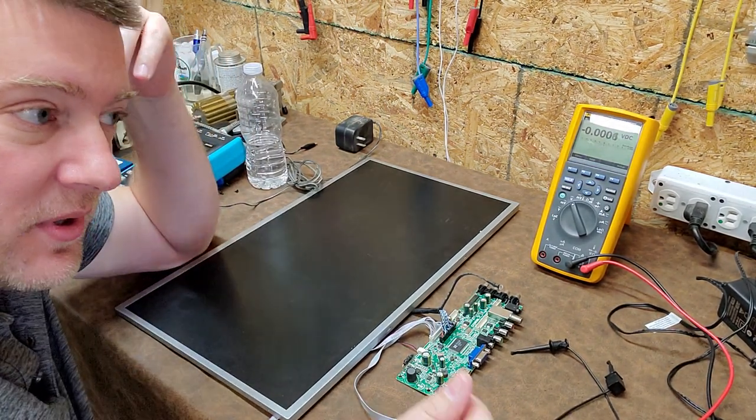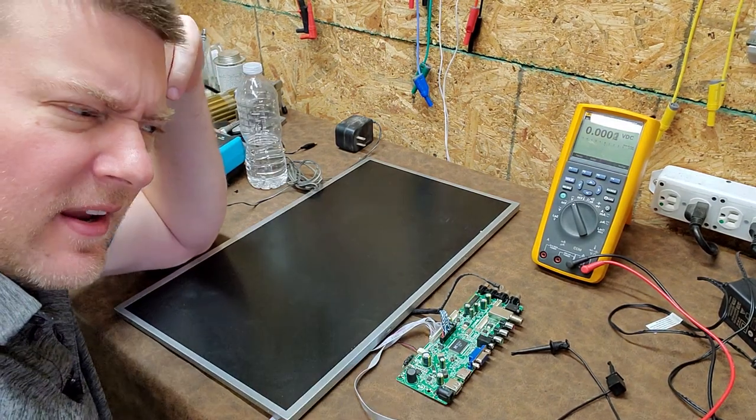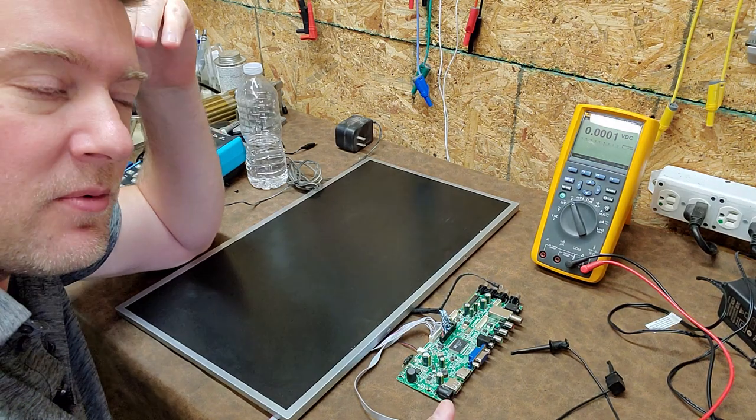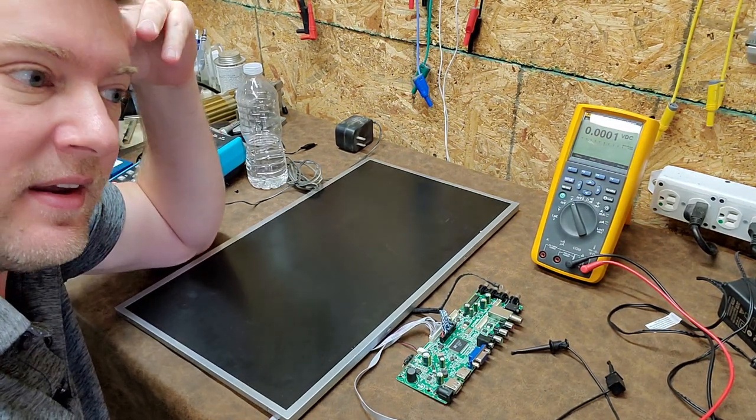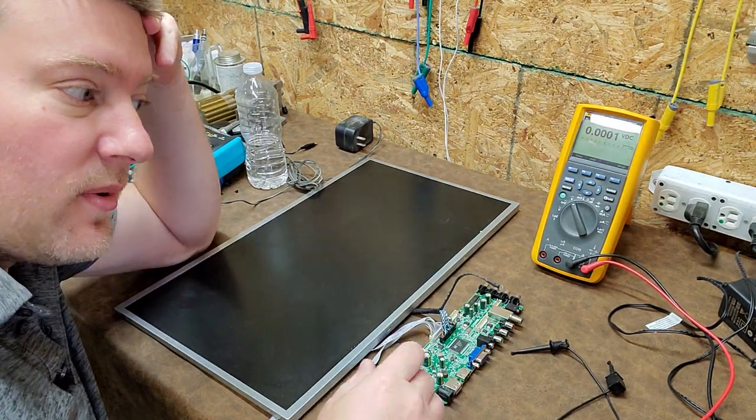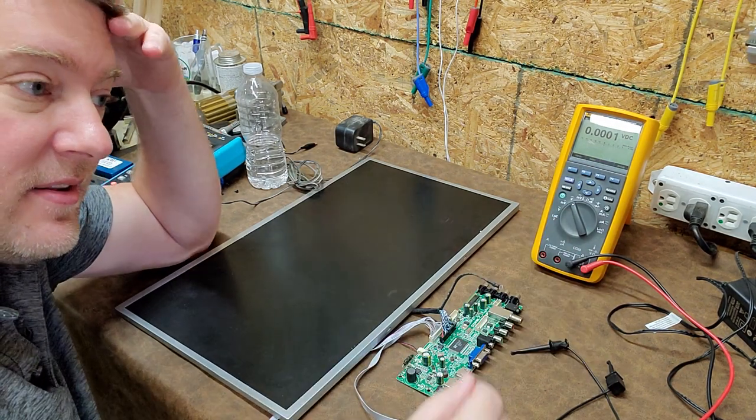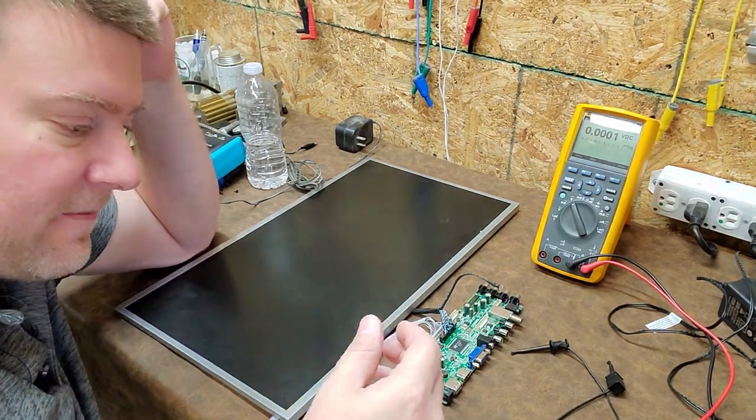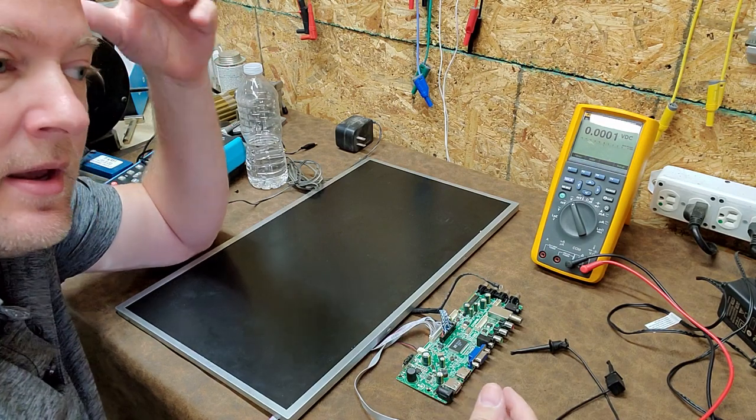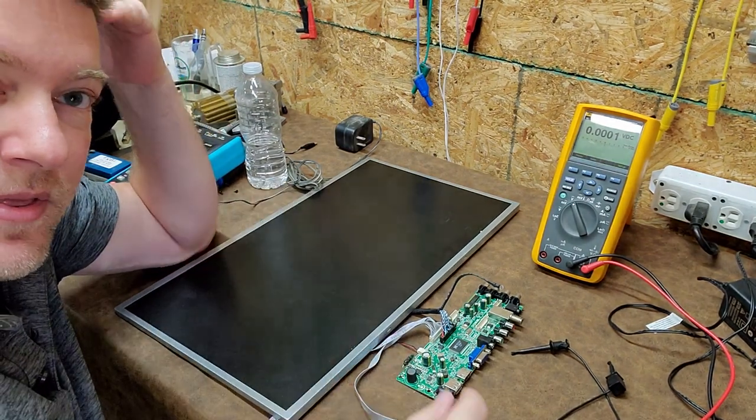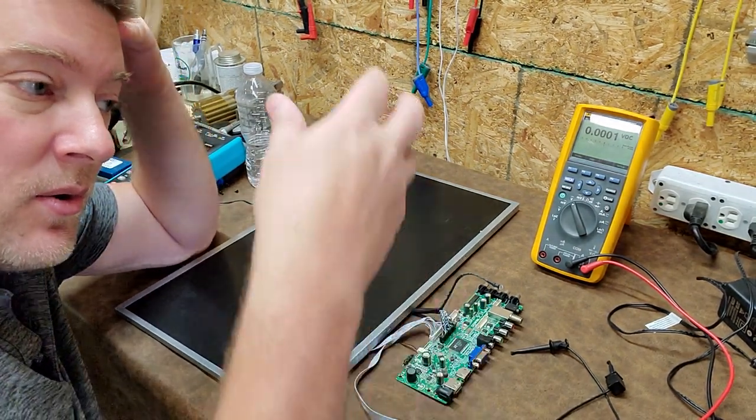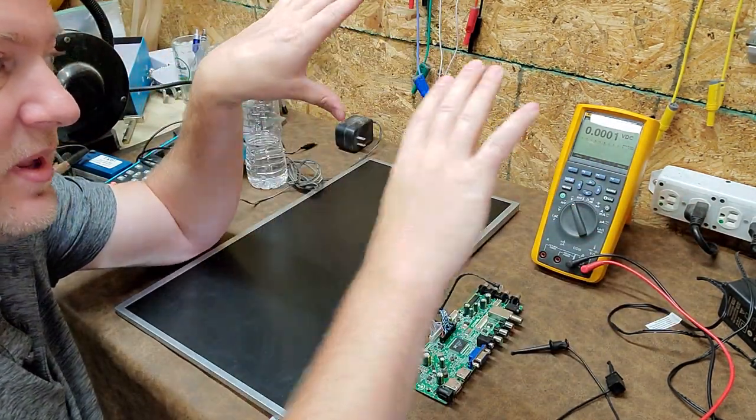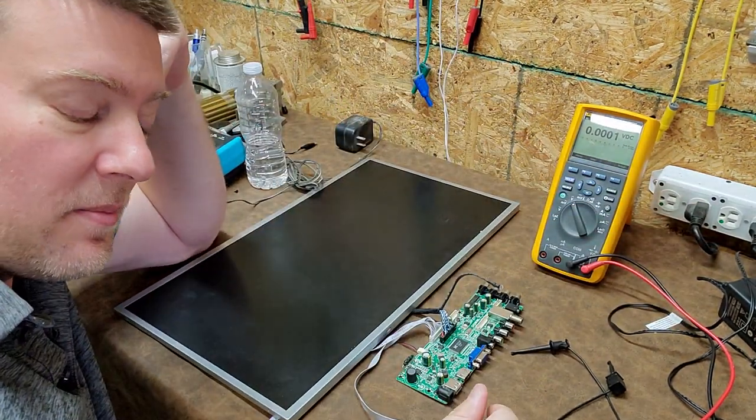Today I've got a medical display, or at least that's what I'd like to think of it. It's really just an RCA TV, but it is technically a medical display because this particular model runs off 12 volts DC. So there is no 120 volt AC input on this display whatsoever. The reason that they run it off the lower voltage DC is because it's much safer to run the cabling up through booms.